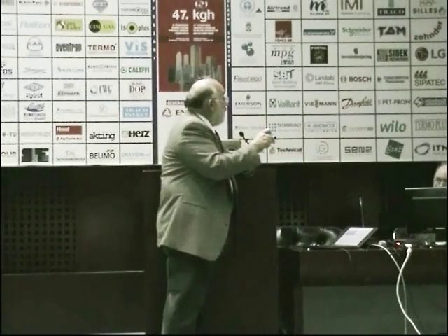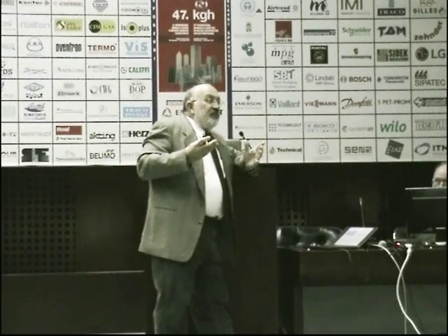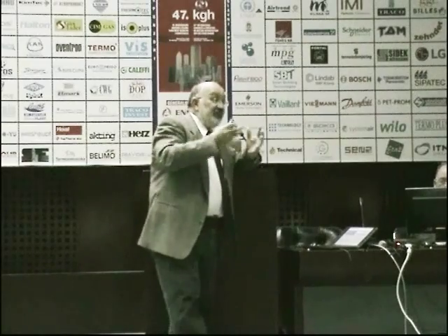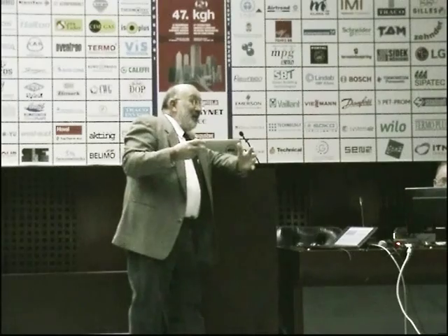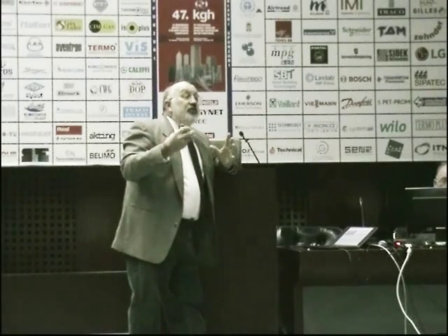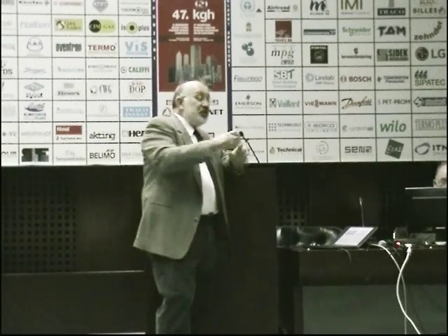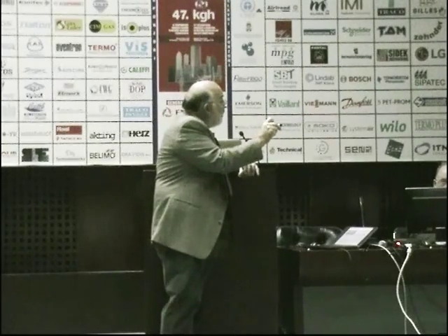And what is happening at the compressor? Where is oil coming from? Oil is always coming from the compressor. That means all oil has to go through the valve. And I will show you a few videos from the valve itself, how that looks like. And you will see some droplets and some ligaments, some very long droplets, which will break into parts, and it will form sort of a misty flow. And that misty flow comes to the compressor discharge pipe. And this would be somewhere here.